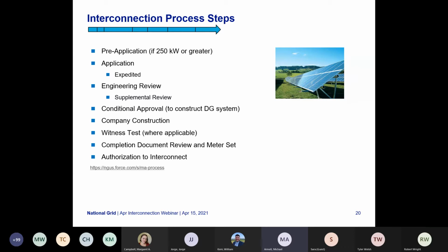The witness test process, typically for our expedited cases, is handled with a commissioning memo along with the as-built completion forms. So when we review all of the completion documents and everything, and inspections are called in, we then call for a meter set. Upon the meter set and the asset registration, we then email out the authorization to interconnect.